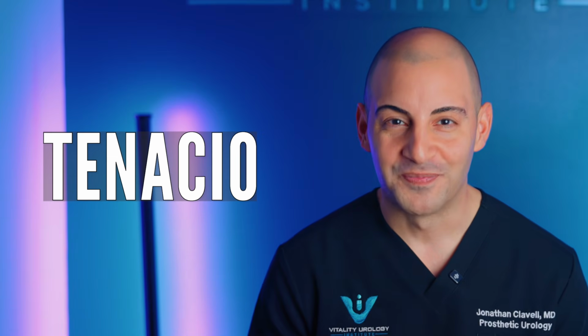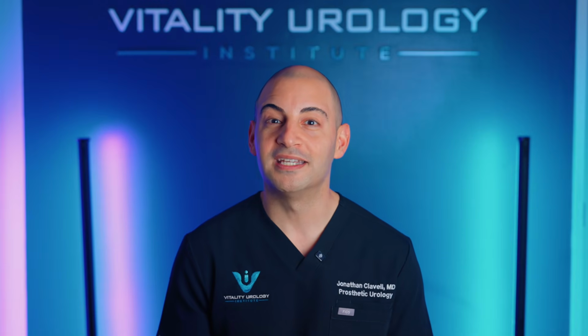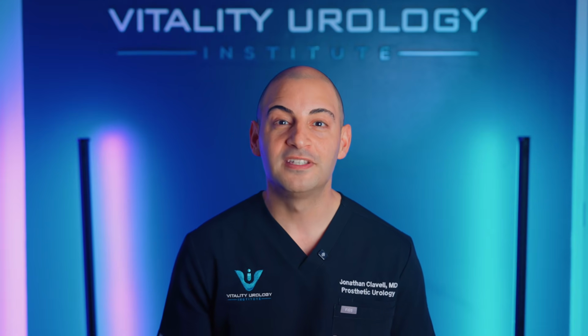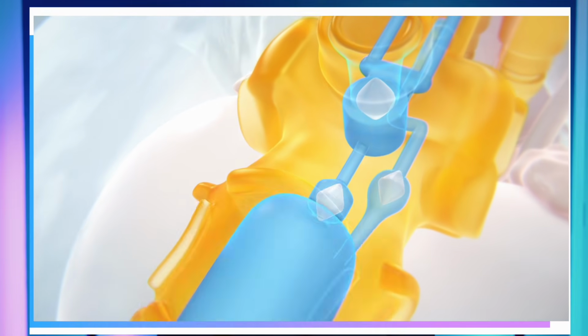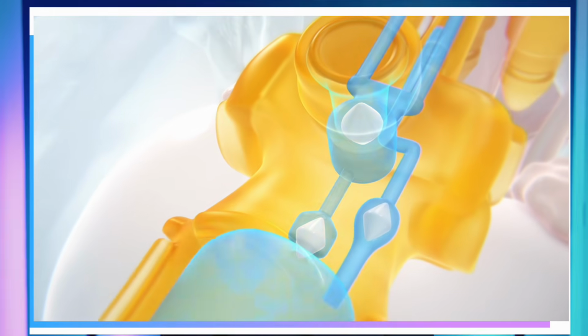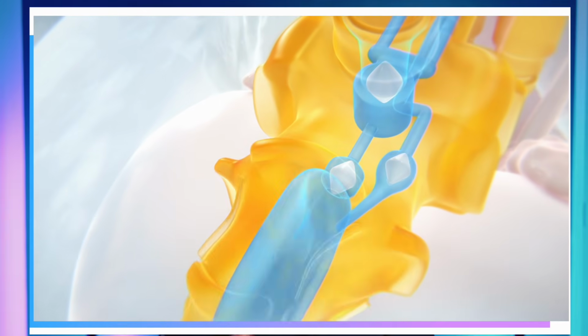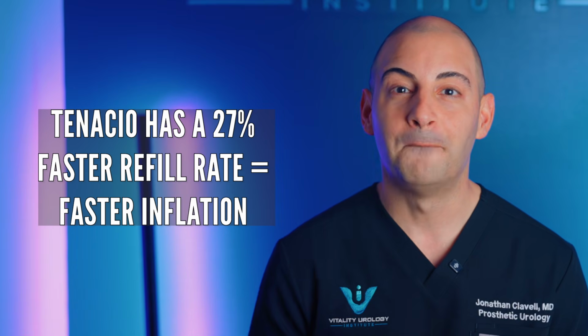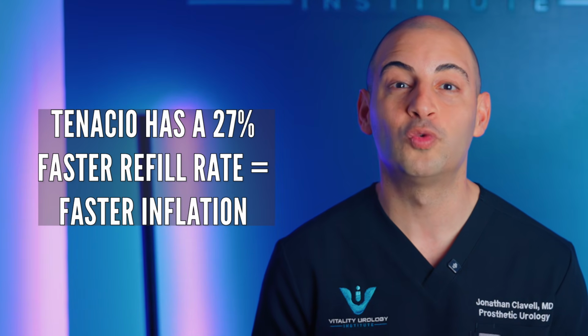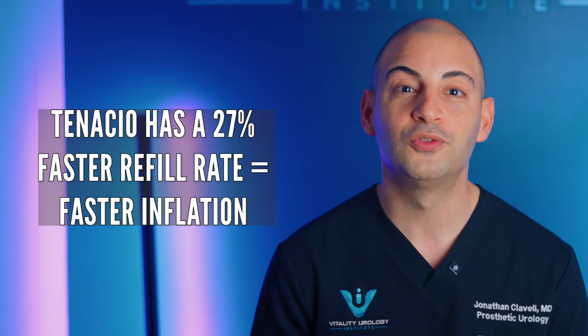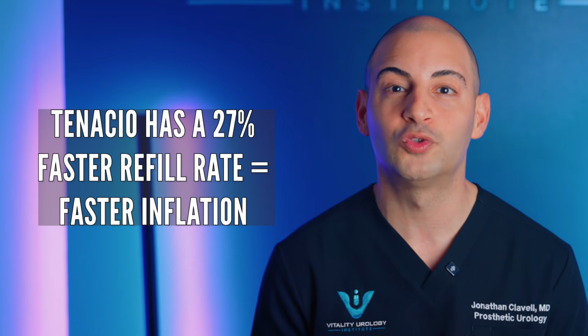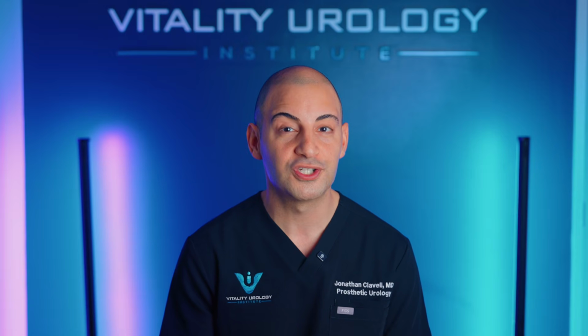Now, Tenacio. The Tenacio pump was released to the market in 2024. Tenacio, unlike MS, has an independent valve system. This means that unlike the MS pump, the Tenacio has a valve to inflate and a separate valve to deflate. They also designed the fluid pathways to be more direct with less twists and turns like the MS pump. These features are set to enhance performance. Boston Scientific claims that the Tenacio pump carries a 27% faster refill rate compared to the MS pump, which can reduce the time required to achieve full inflation. They also claim that this pump allows for quicker and more efficient inflation.